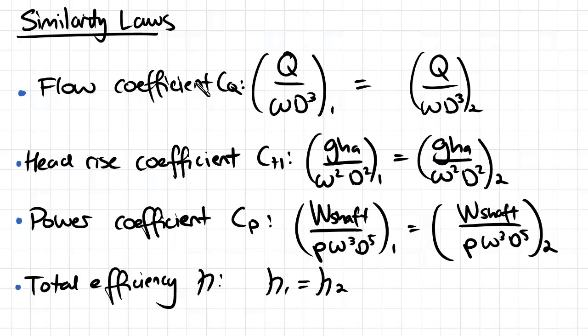So our flow coefficient, that is the flow rate divided by the angular velocity divided by our diameter cubed. And then we've got our head rise coefficient, that's equal to gravity times our gain in head divided by our angular velocity squared divided by our diameter squared, and that remains constant.